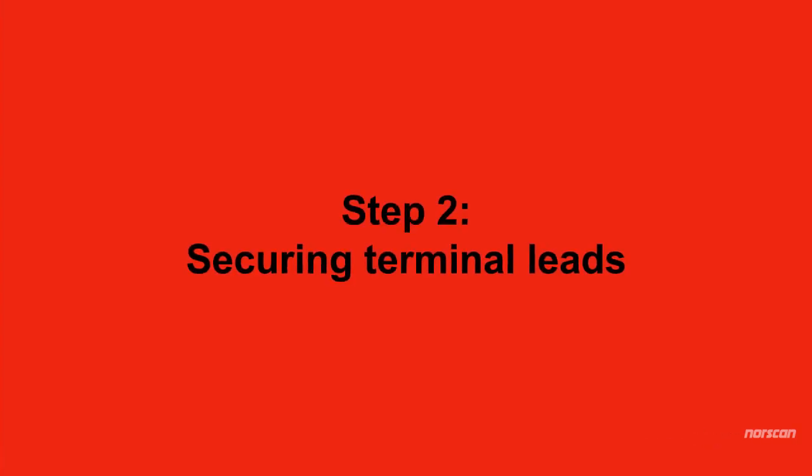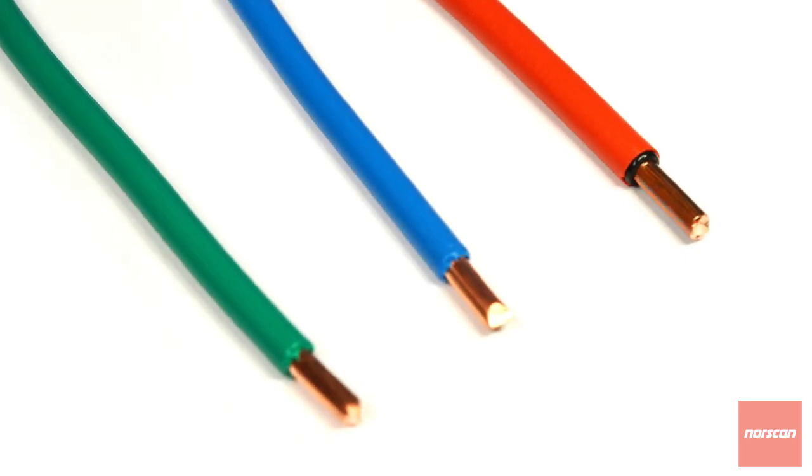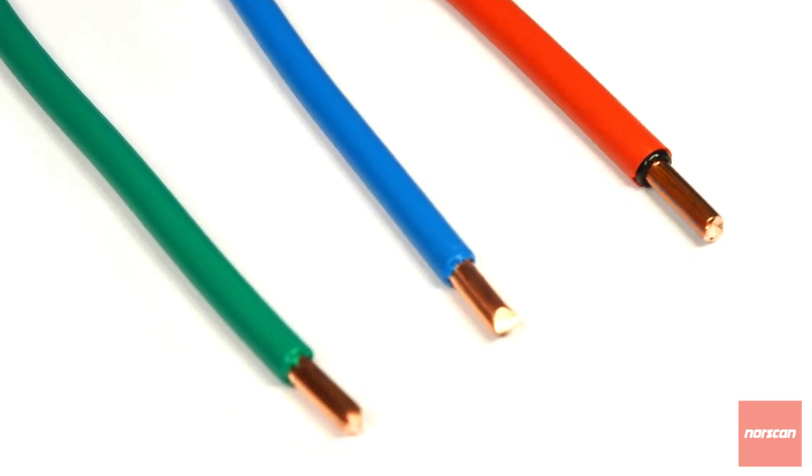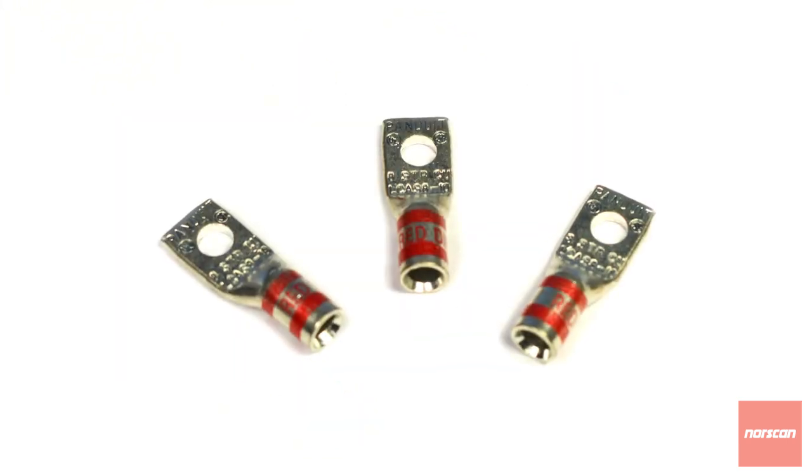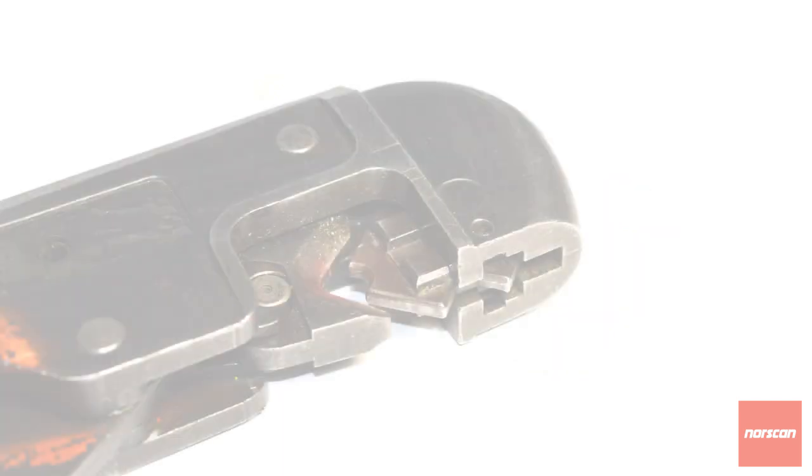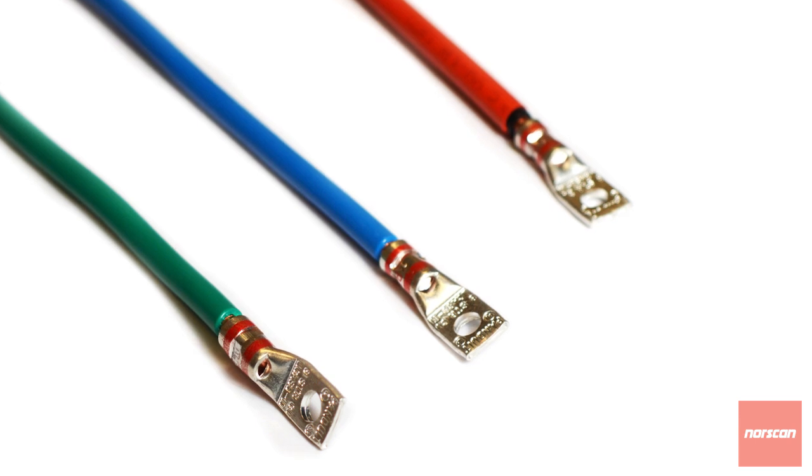Step 2: Securing Terminal Leads. Strip 3/8 to a half inch of insulation from each of the three leads. Insert one terminal lead onto each cable, then using a number 6 crimper, crimp the terminal connection securely.